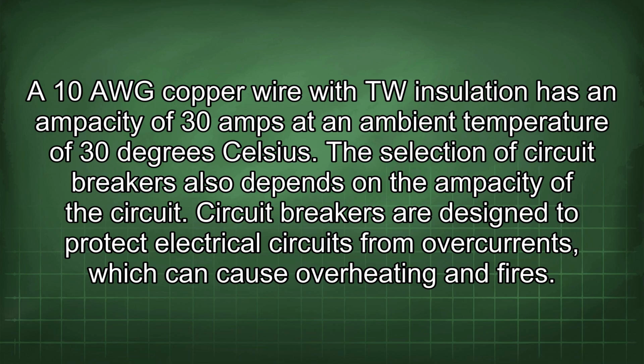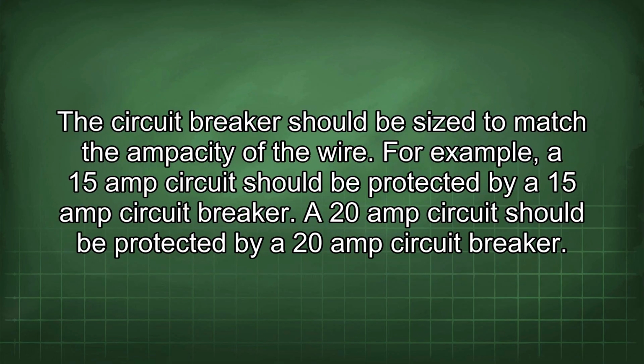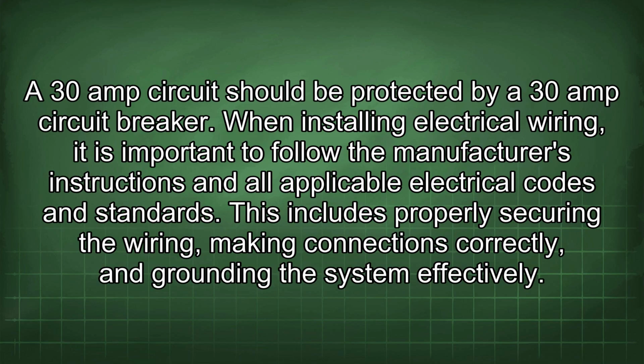Circuit breakers are designed to protect electrical circuits from overcurrents, which can cause overheating and fires. The circuit breaker should be sized to match the ampacity of the wire. For example, a 15 amp circuit should be protected by a 15 amp circuit breaker. A 20 amp circuit should be protected by a 20 amp circuit breaker. A 30 amp circuit should be protected by a 30 amp circuit breaker.